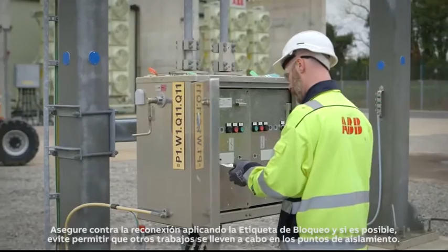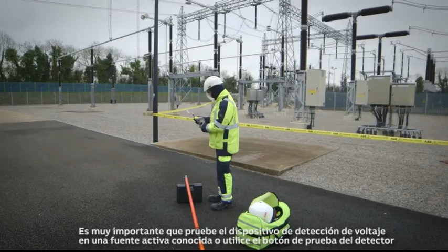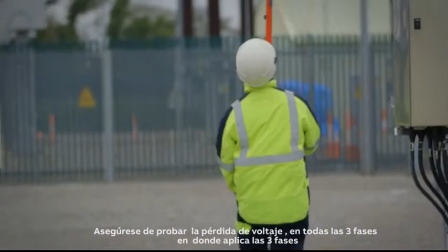Step 4. Verify the absence of operating voltage. Utilize only properly rated and calibrated voltage detection devices and wear the proper PPE identified in Step 1. It is extremely important that you test the voltage detection device on a known live source or by using the detector's test button if designed into the device. Then test for the absence of voltage. Ensure to test for loss of voltage on all 3 phases where 3-phase applies.